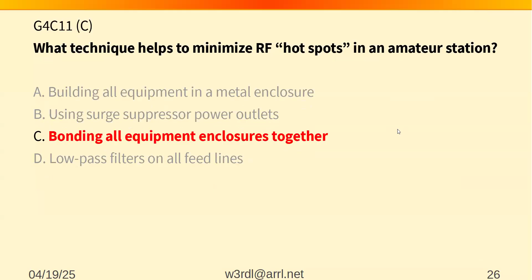Just to comment on grounding, I did some work for Bonneville Power long ago, and the guys we worked with told about the safety precautions they had. They talked about grab potential or step potential, and had two-inch copper plate floors to keep the potential difference between two rubber-soled tennis shoes, special issue, below 300 volts when they had faults. When they had a ground fault it was a serious problem, transformers the size of a freight car would explode. So grounding can be very important indeed.